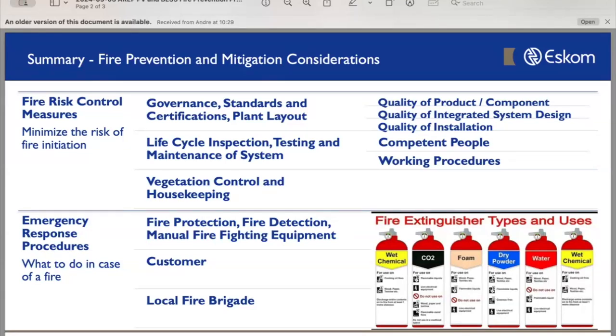In remote areas or areas with vegetation control issues, we've seen many fires where a veld fire or brush fire next door becomes an exposure fire to whatever we've built. So vegetation control matters, depending on location, plant type, and size. Vegetation control plus housekeeping also matters - positioning these things where there are oily rags or other fuel combination aspects nearby is a problem. I've even seen LPG gas installations at shopping malls positioned next to the dumpster area, where an exposure fire to those gas cylinders could have horrific consequences if not controlled.